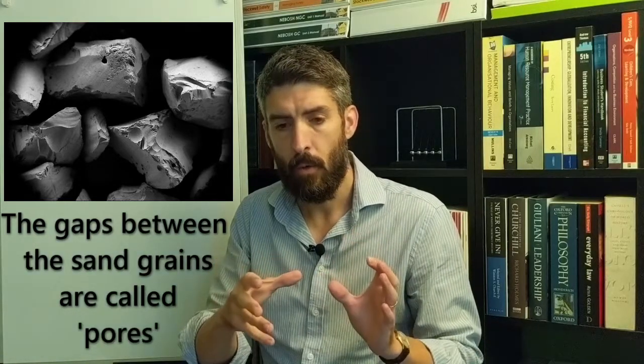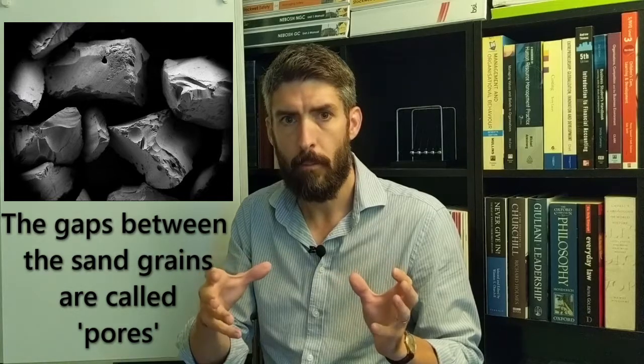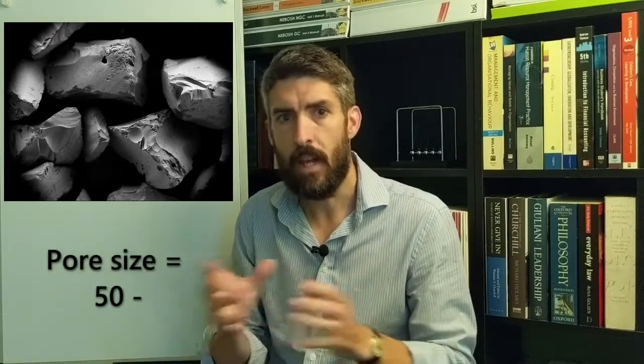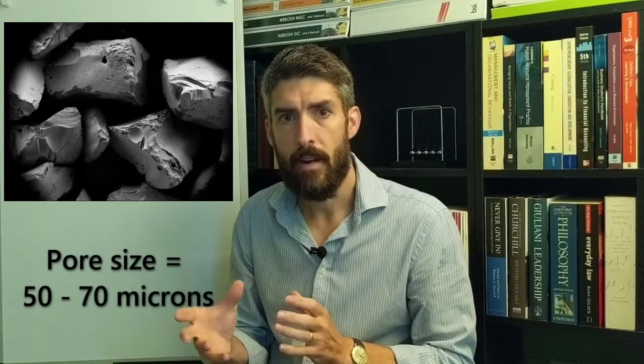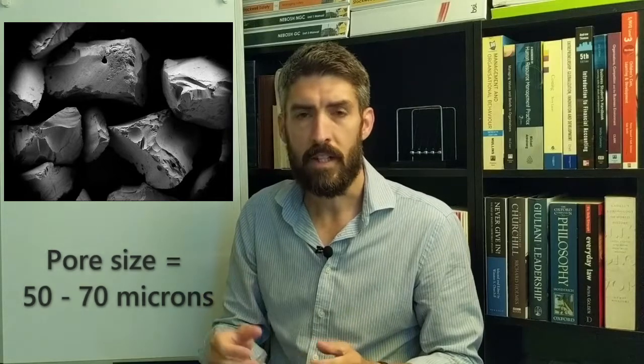In a typical commercial swimming pool filter, the gaps that get created, the pores, are going to be in the region of 50 to 70 microns in width. A micron is a thousandth of a millimeter, so we're talking about between 50 and 70 thousandths of a millimeter.